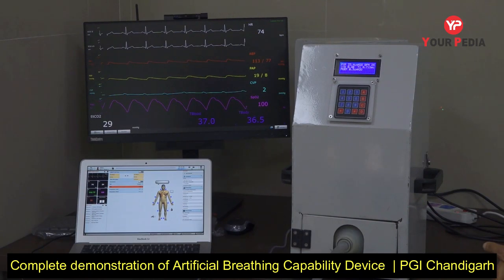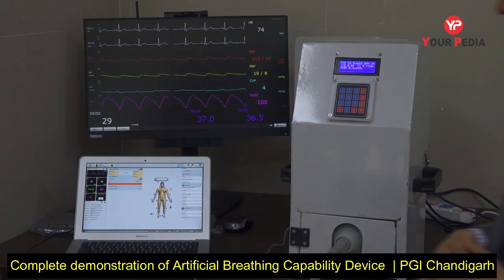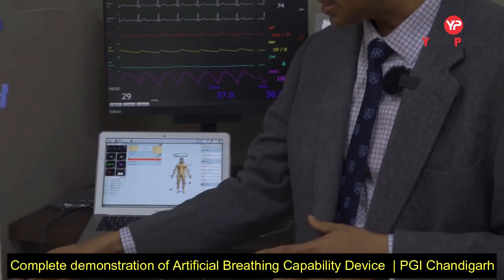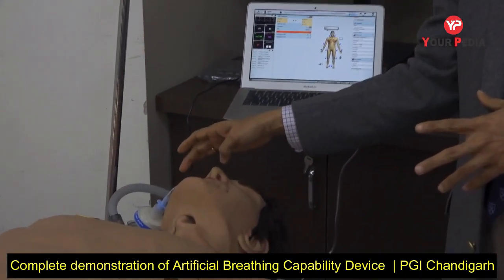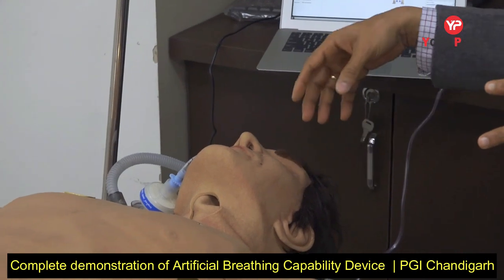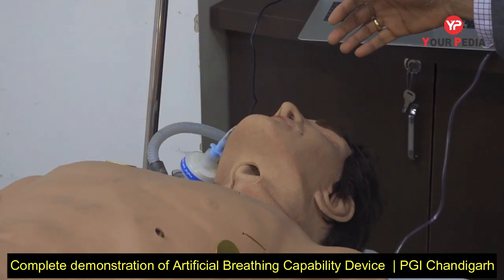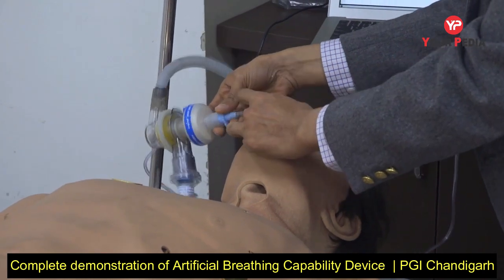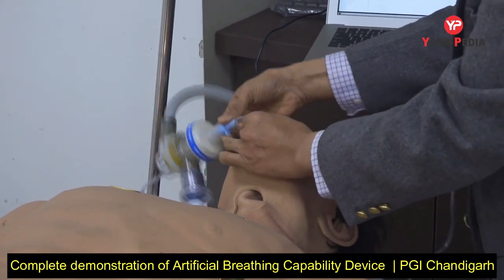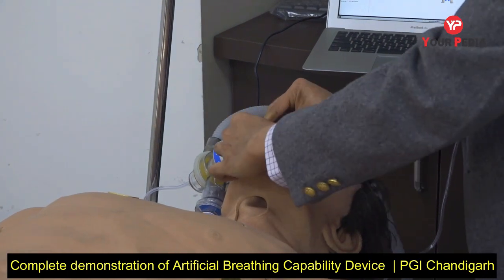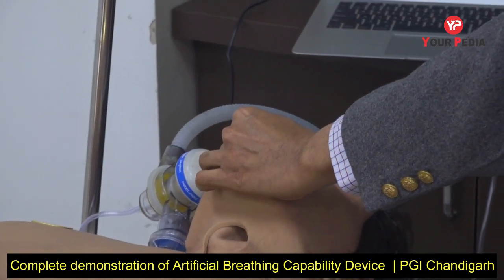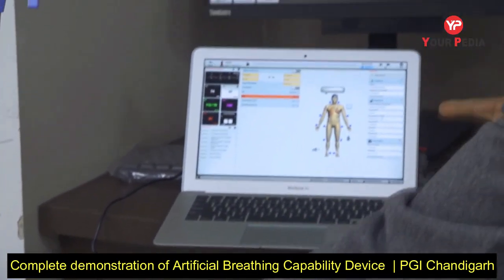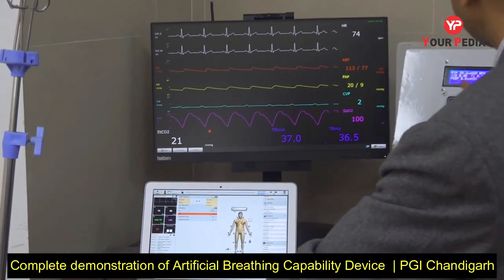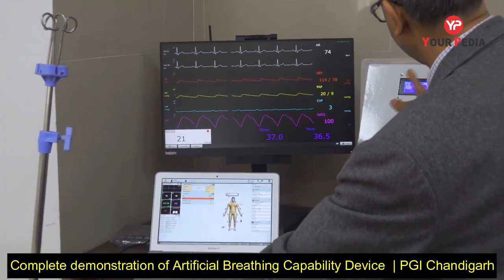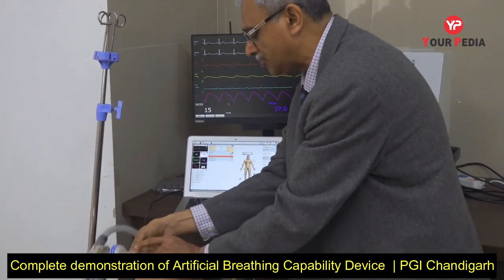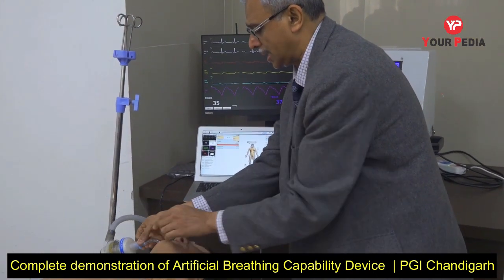The device also has several other novel features which have been built in for safety. If there are endotracheal secretions which are jamming this endotracheal tube which is inside the patient and a tube blockage occurs, we will now simulate a tube block by compressing this tube over here, so to prevent the airflow. So this is a real world situation in which we often find this. You can see that there is a decrease in the flow, so the patient monitor has picked it up, and you find that the ventilator is delivering a higher pressure than expected, and an alert sets in until we relieve this tube block. This will be continuing like that.